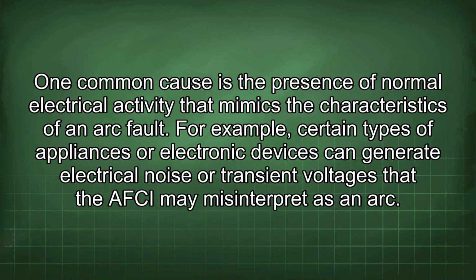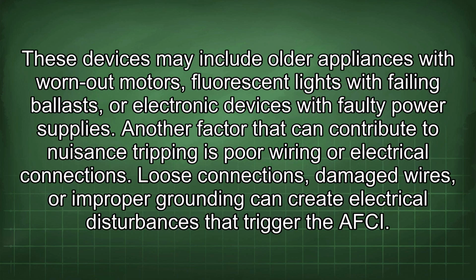One common cause is the presence of normal electrical activity that mimics the characteristics of an arc fault. For example, certain types of appliances or electronic devices can generate electrical noise or transient voltages that the AFCI may misinterpret as an arc. These devices may include older appliances with worn-out motors, fluorescent lights with failing ballasts, or electronic devices with faulty power supplies.